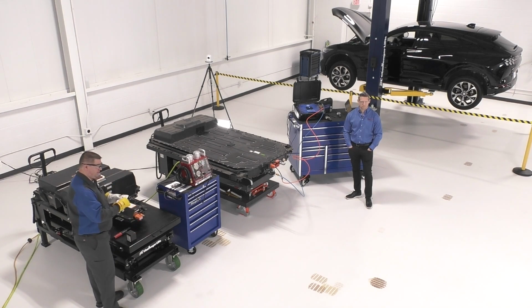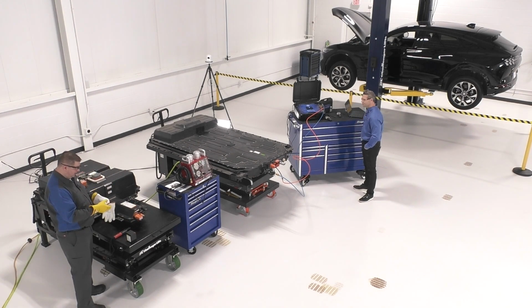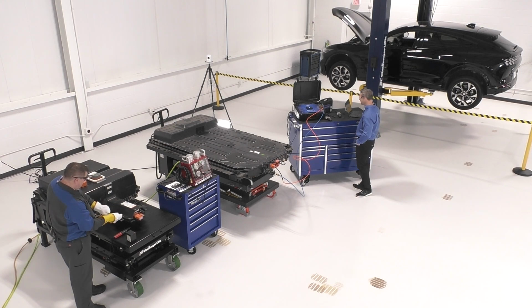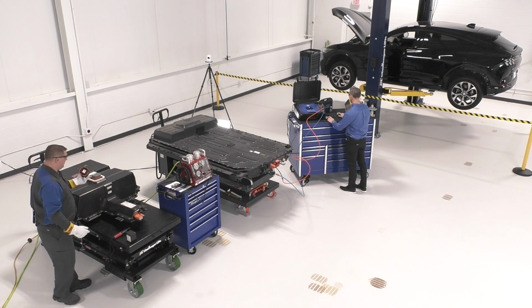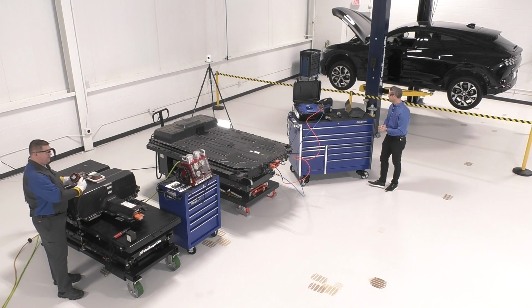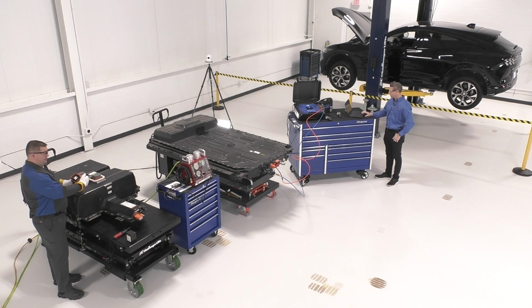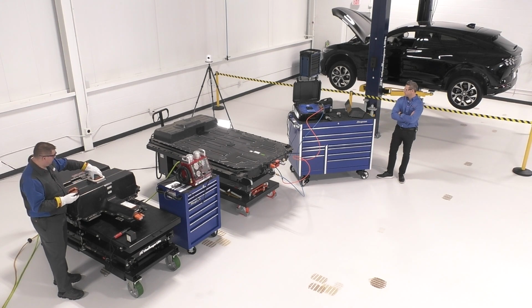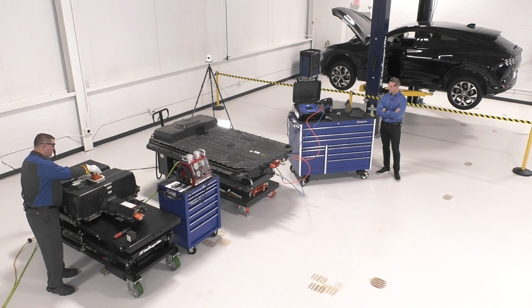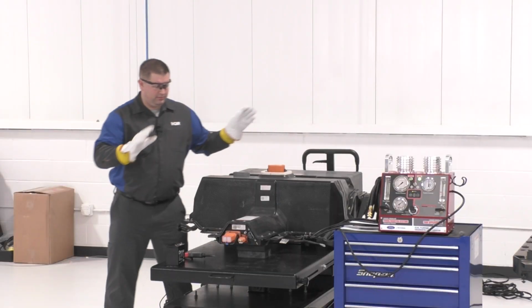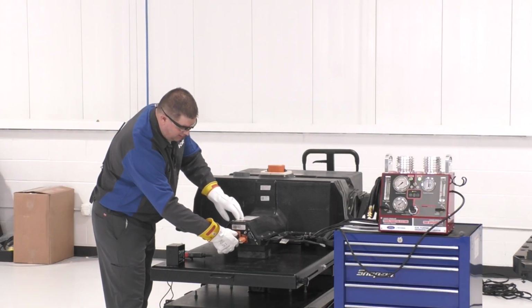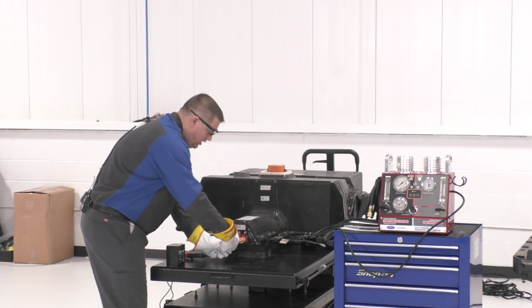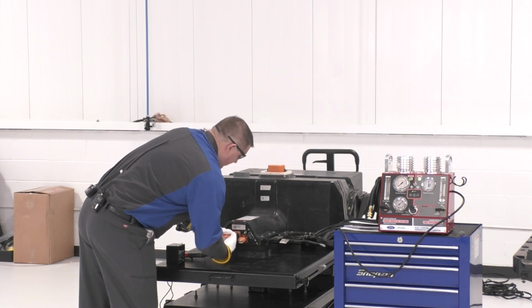Yeah, as you were talking there, I was getting prepped. I checked my gloves to make sure they're good because we're going to have to plug in this high voltage disconnect. What this does is it effectively splits the battery into two sections, taking the battery voltage and cutting it in half so we have two separate sides. In order to do this testing, we have to put this service disconnect plug back in so it seals this top off. So I'm going to go ahead and put this back in. Now just to verify, I'm going to come back over here to my main plug and do a zero potential check real quick. I'm going to pull this plug off and grab my 2-pole tester.